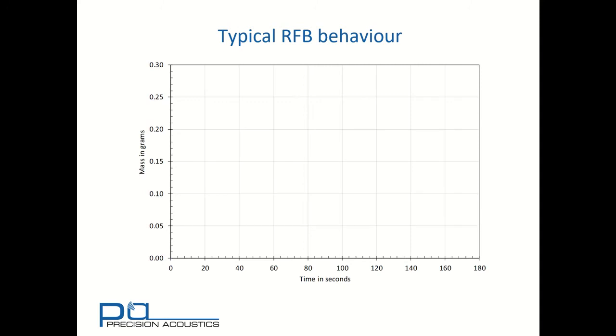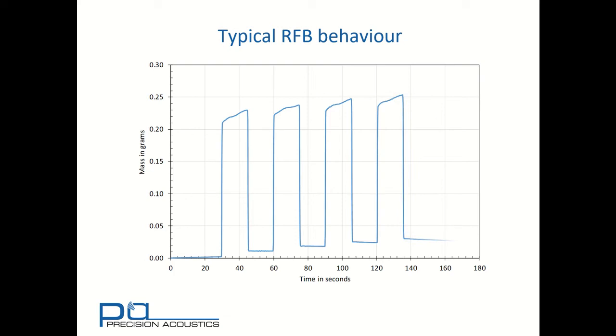Let's look at the typical trace that we may see from a radiation force balance. Here we'll be looking at the effective mass reported by the balance as a function of time. In fact, what we will do is switch the transducer on and off for four separate cycles. We note that if we look at each of the on cycles, immediately following the ongoing transition, there is a drift upwards of the trace.